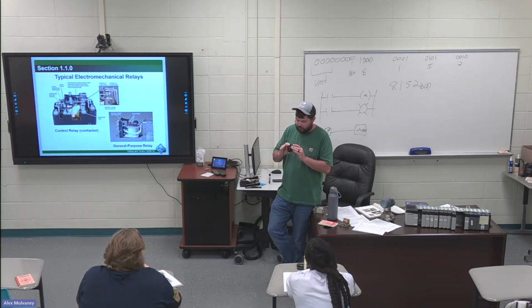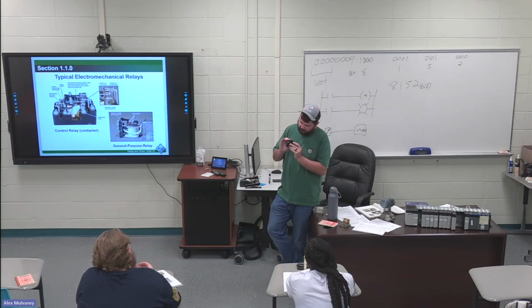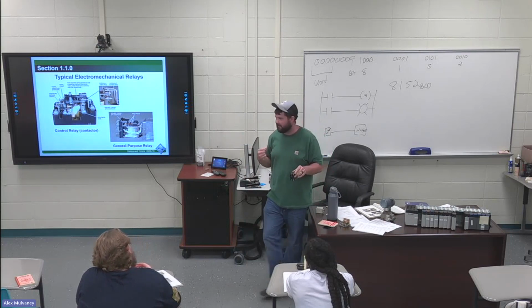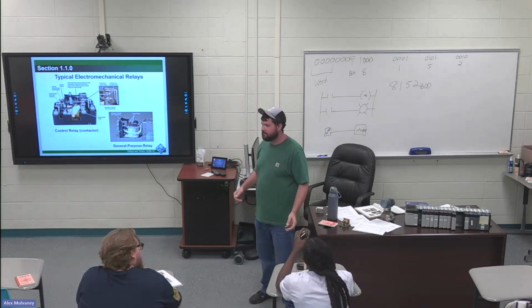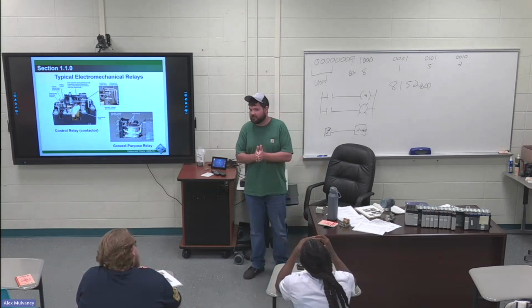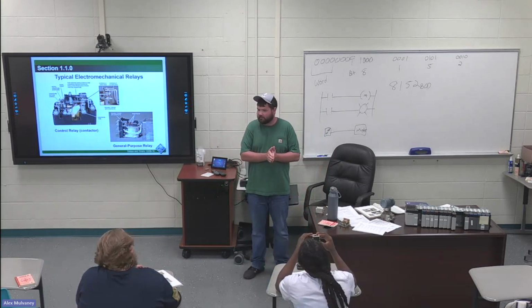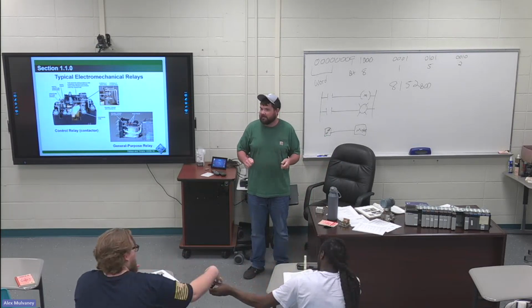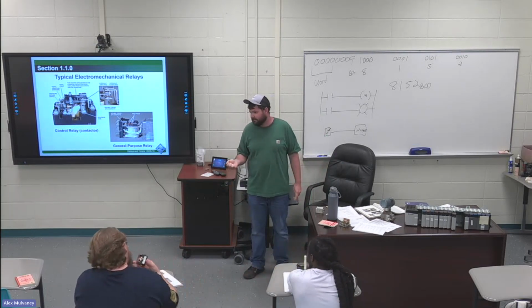Take a look, the contacts are right here on the front. You can push those in, but you need to shine your cell phone light in there to see the pitting that happens. And the more pitting there is, the less smooth that surface is for the contacts, and the less contact it's going to make. So the less contact I have between my contacts, it increases my resistance.